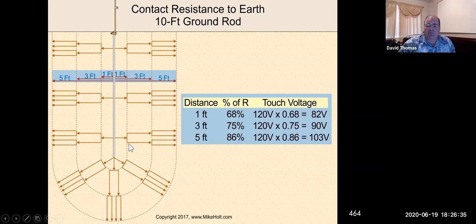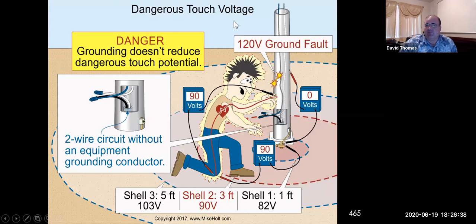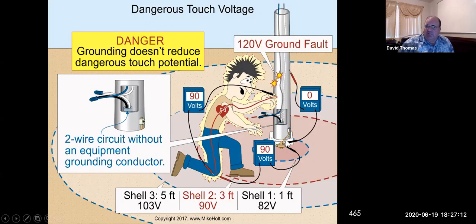Anyway, we'll leave it at that. Yeah, this is that scenario with the little girl having the two-wire circuit, no ground in here, and how Earth itself will have voltage dropping through here. So you will have a certain amount of voltage. In this case, he's in the second ring here, where the second ring is 3 feet away. Actually, it says 75%, so you have about a 90 volt drop here. From the pole out to the outer edge where he's got his knee, it's supposed to be 3 feet distance. There's 90 volts of voltage drop occurring on the body.